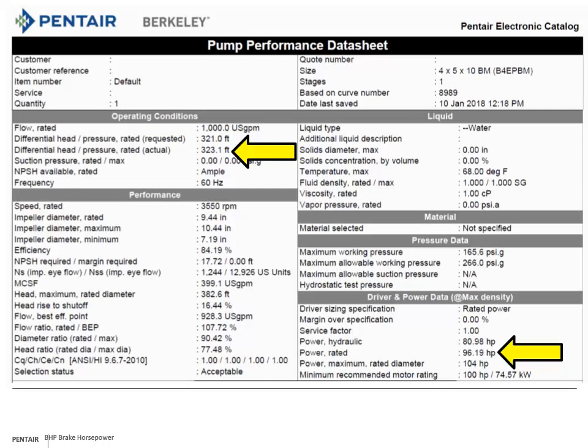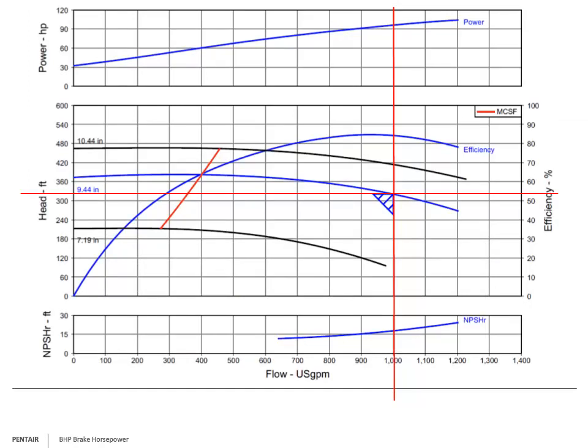The information has been given to us and we have been able to calculate the head easily. Now let us take the opportunity to use a sizing program and pull up a curve. Reviewing the curve, you can see we are spot on. Will the data given guarantee this is in fact the submersible pump curve of the pump we are testing in the well? No, but we have gained two pieces of information: the total dynamic head to test the pump, and the parameters we need to size a new pump should we need to.